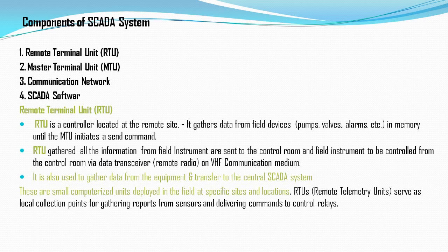The RTU is a controller located at the remote site that gathers data from field devices — temperature, flow, pumps, valves, and alarms — and stores it in memory until the MTU initiates a command. The RTU sends information from field instruments to the control room via transponder, radio, or VHF communication. Think of the RTU simply as a gathering device — collecting signals like temperature, pressure, level, and flow from the site.